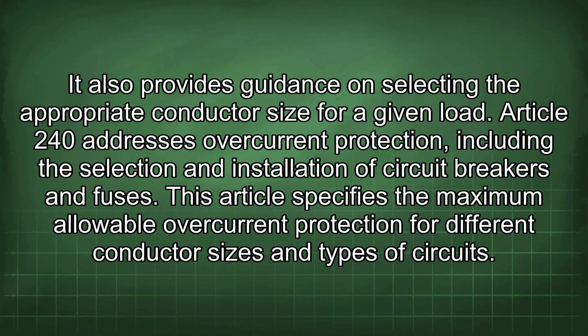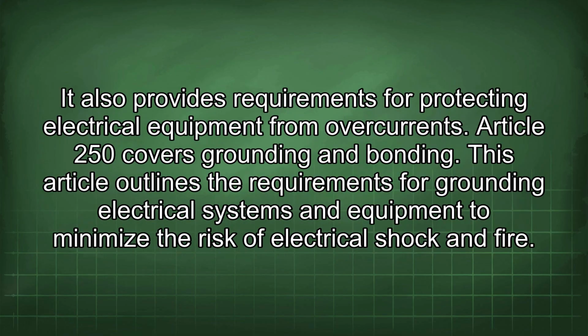Article 240 addresses overcurrent protection, including the selection and installation of circuit breakers and fuses. This article specifies the maximum allowable overcurrent protection for different conductor sizes and types of circuits. It also provides requirements for protecting electrical equipment from overcurrents.